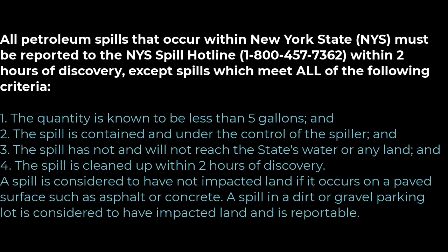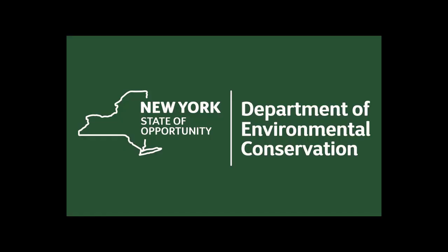The spill is contained and under the control of the spiller. The spill has not and will not reach the state's water or any land. The spill is cleaned up within 2 hours of the discovery. You must call the New York State Spill Hotline at 1-800-457-7362 within 2 hours of the discovery.